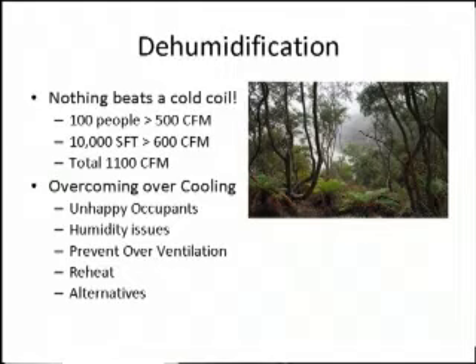So we talked earlier about the air coming in mixed with water vapor, hitting a cold coil, condensing. That's our primary means for dehumidification. So that's why we're talking about nothing beats a cold coil. For every 100 people, from the numbers on the last slide, the ASHRAE numbers, we need 500 CFM, and those people need about 10,000 square feet, 100 square feet each. So we need a total of 1,100 CFM coming into the facility to ventilate for those 100 people.